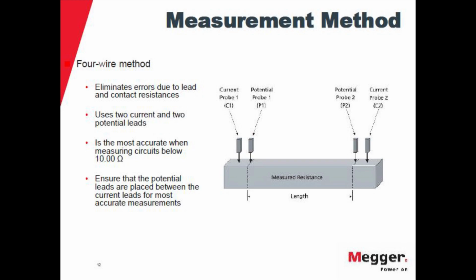And one thing that you always have to consider is that the potential probes have to be always inside the current that you are applying. Because if you put the probes outside the current, in addition to the voltage drop due to the resistance, you are going to measure the voltage from the instrument that is applying to circulate the current. So that will influence your result. So when you have separate leads, you have to always connect the potential leads inside the current connection. There are leads that come with everything integrated, so that won't cause any problems.